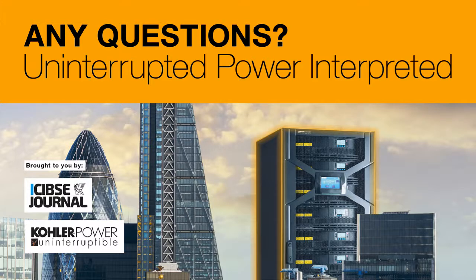As far as 6-month maintenance is concerned, it's more about ensuring that the battery is going to work when you need it. Batteries can be the most unreliable part of a UPS system, so as part of that maintenance, we should be checking all those batteries. So yeah, you want to know that they're going to work when required. Now, if the customer has their own monitoring system connected, they can do that very simply themselves, and it will automatically do that during automatic battery tests of the UPS if they need it to.